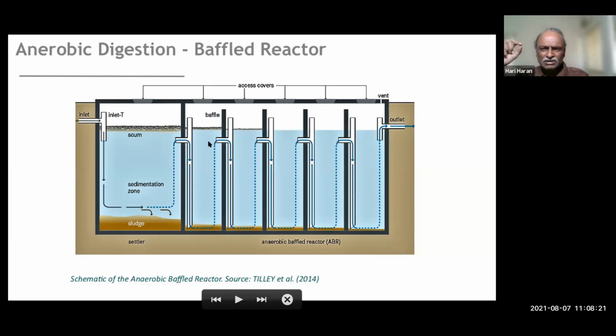At the business level, this is a question you have to ask anybody you're talking to. Let's say you've got 100,000 liters of water discharge, and you want to plan for a new building or an existing building. When you go to any of these people, they will say, okay, 100,000. You have to ask them what the size of your tank is. Typically they will take 1:2.5, 1:3, and if they're really good, they will say 1:2. That is, if I have 1 lakh liters, they will take, say, 2 lakh liters as the total sizing of these tanks that he is putting up here. Now, the sequence will be more or less the same.